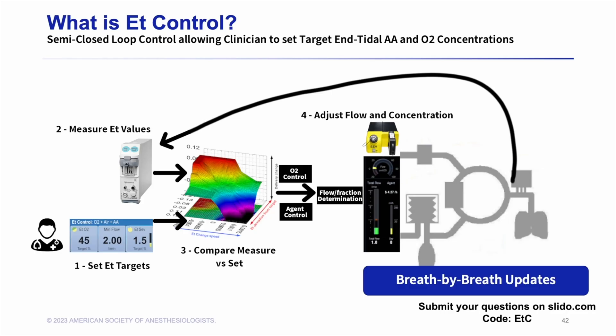So how does this thing actually work? Dr. Kennedy gave a pretty good overview — I'll try to go one level deeper. The first thing you do with the feature, as you see here, number one, you set those end-tidal targets. You set an end-tidal oxygen and agent target, and you set your minimum flow value.